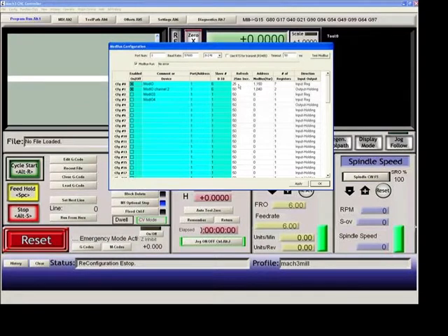And we can also tell it how often to refresh the data. So on 25 milliseconds, this tells the serial system to refresh this configuration 0 every 25 milliseconds. We are telling it the Modbus variables are located at 1150, and we want 7 of them. So the first 7 16-bit words of the Modbus will be transferred in from address 1150 to addresses 0 through 6 on the plug-in Modbus, which is what I've named it, plug-in Modbus registers in configuration 0. This will all make better sense in a moment.